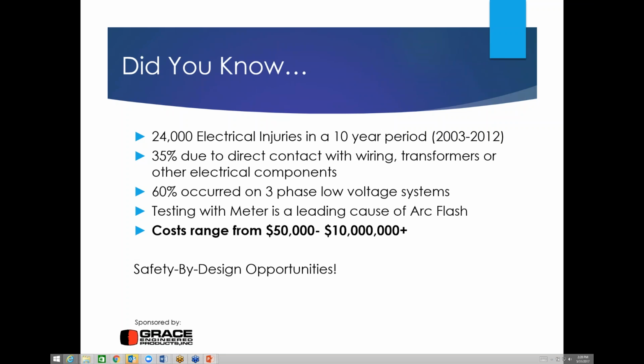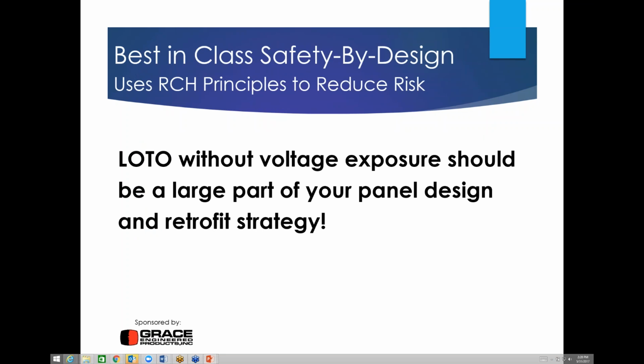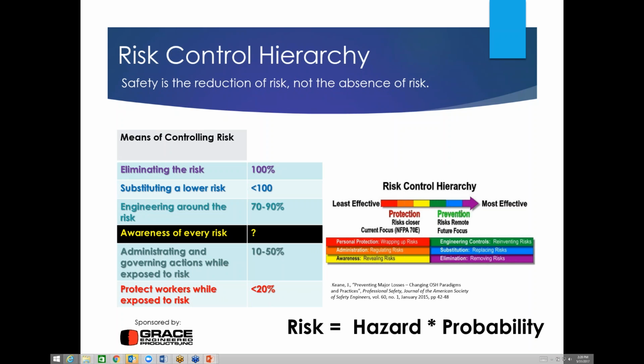So really what we want to do this afternoon is just talk about some of the best-in-class safety by design opportunities that exist and what that might look like. As we move forward, one of the things that we really need to be thinking about heavily is the opportunity to do lockout tagout without voltage exposure, and it should be a large part of our panel designs today and our retrofit strategy. So a few things to keep in mind with that is the application of the risk control hierarchy and the opportunities that exist to reduce the risk or eliminate risk in the process.